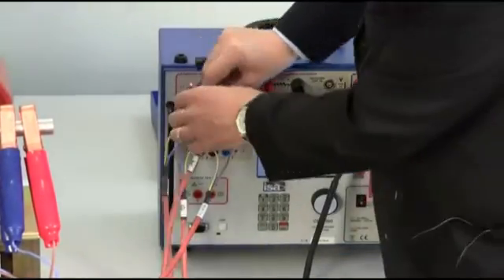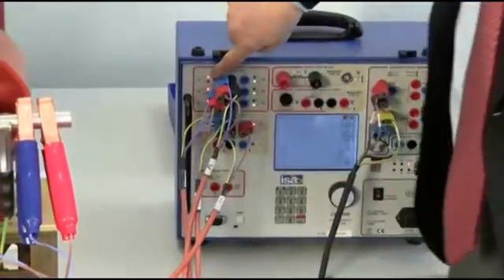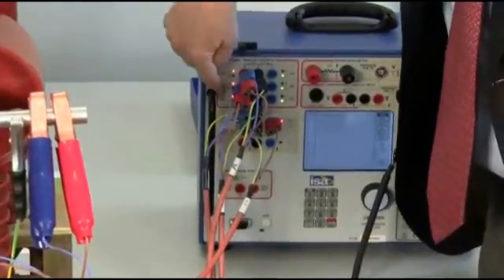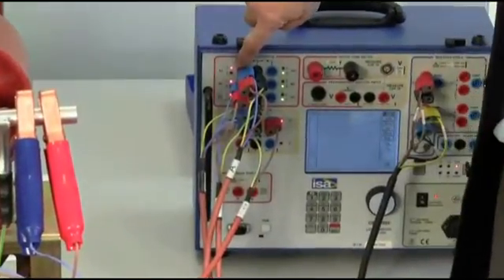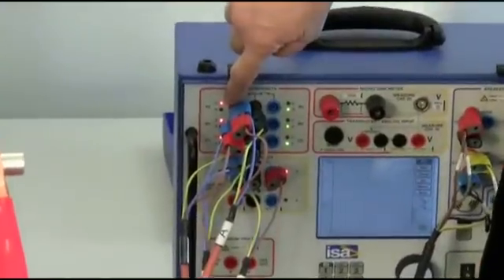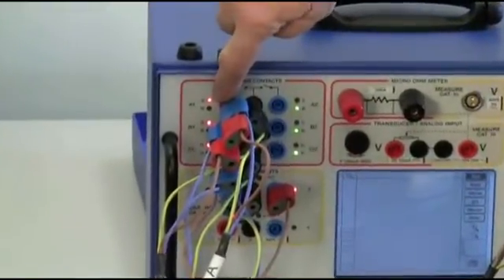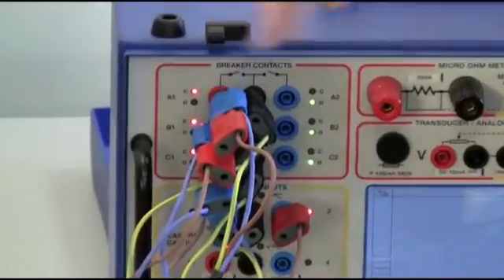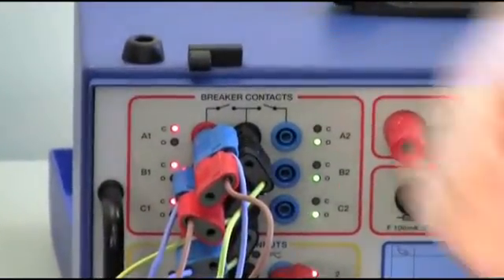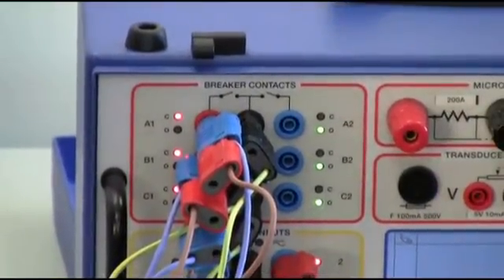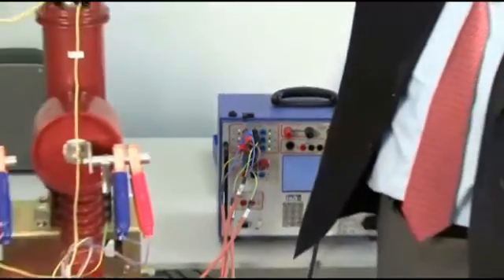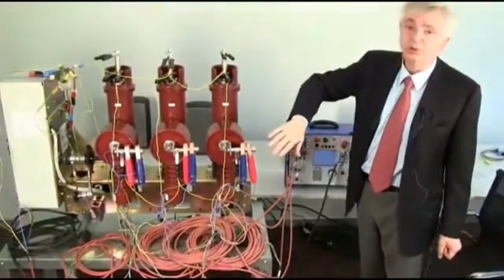It is not easy to be seen, but this one and then the other two LEDs are on, telling me that the circuit breaker is closed. Why is it closed? It should be opened, we have opened it. It is closed, it is seen closed because I still have the grounding on both sides.